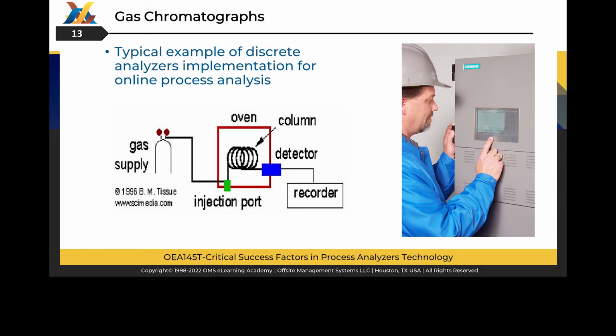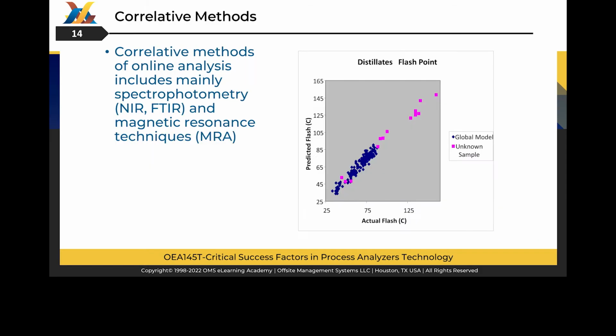Despite its high maintenance requirements, this technology is the only available solution in many applications, where multiple components shall be measured with high accuracy. This method also requires the supply of high-quality carrier gases, hydrogen, nitrogen, helium, or argon with 99.995% or higher purities. Correlative online analysis methods are faster and less expensive and include spectrophotometry, NIR, FTIR, and magnetic resonance techniques, or MRA. However, validation of correlative analyzers against standard laboratory methods is only possible using special ASTM procedures. These factors should be seriously considered at a time of analyzers' performance validation and acceptance.